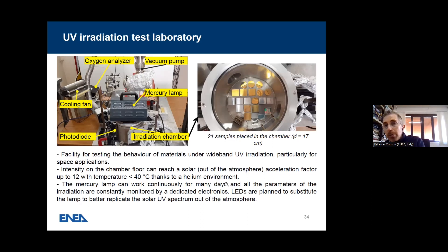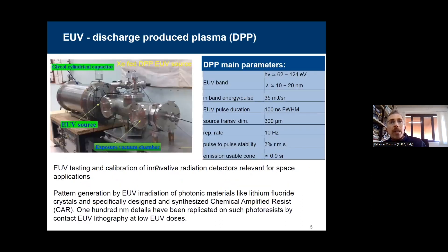The Mercury lamp can work continuously for many days and all parameters are constantly monitored by dedicated electronics. It is planned to replace the lamp with LEDs to better replicate the solar ultraviolet spectrum. This is used for example for irradiation related to materials exposed to solar radiation. Another facility is the discharge-produced plasma extreme UV source — from 62 up to 124 electron volts with 35 millijoules per steradian, duration 100 nanoseconds full-width at half maximum. This is for testing and calibration of innovative radiation detectors relevant for space applications, and also for pattern generation by extreme UV radiation of photonic materials like lithium fluoride or chemical amplified resists.